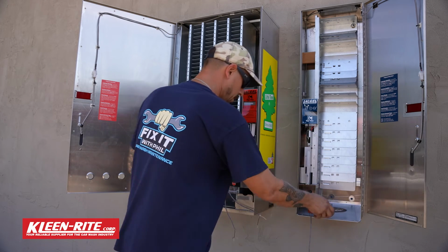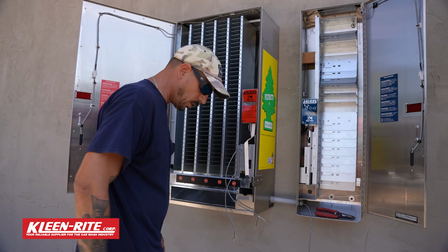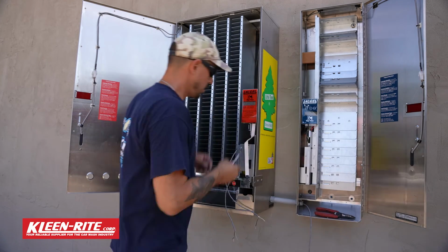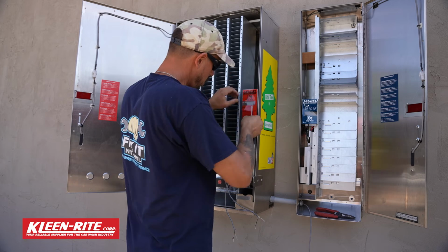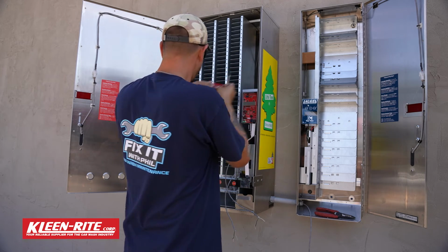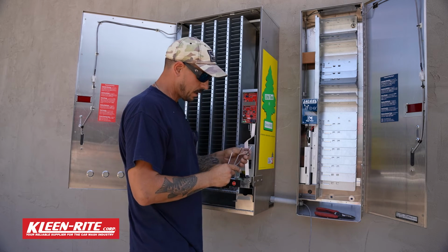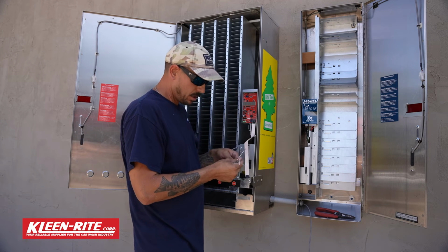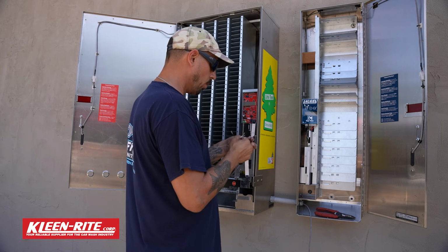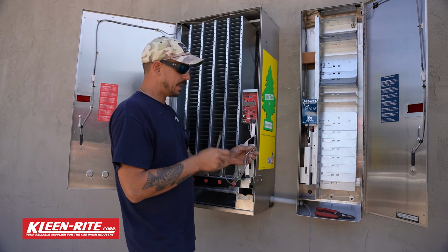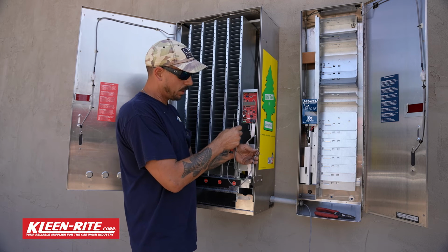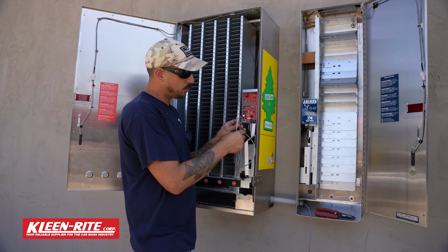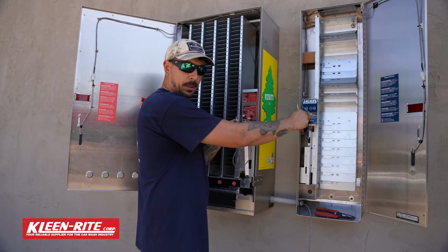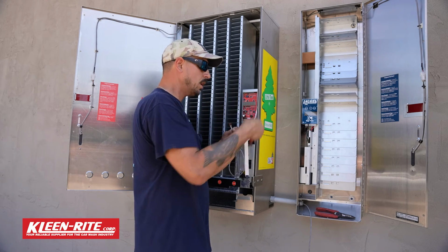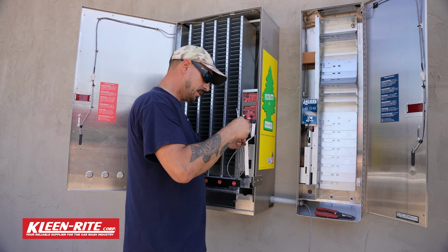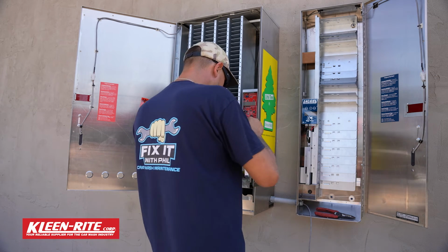So now we're going to daisy chain these together, and what I mean by that is I am going to land both sets of these wires on one board, and that effectively is going to take power from the transformer to this board and also apply it to these wires and bring it over and apply it to this board as well. Instead of having to pull two wires through, the transformer carries more than enough power for us to be able to do it this way.